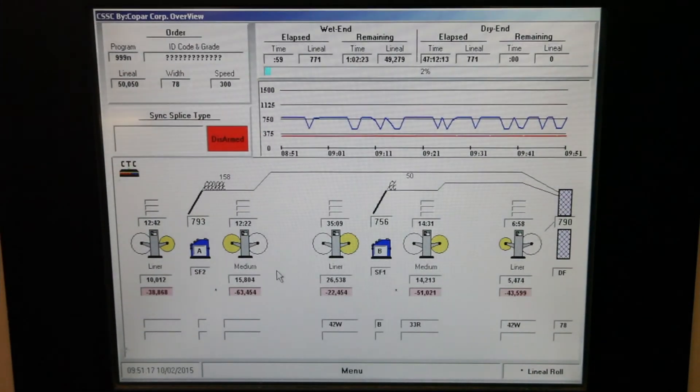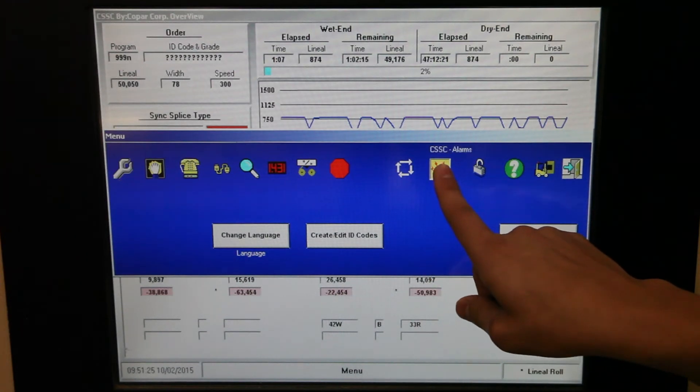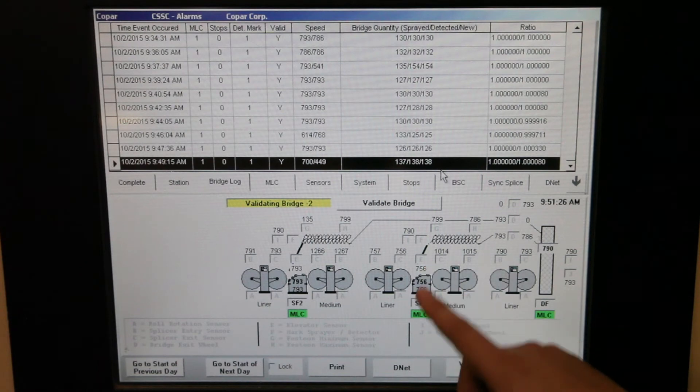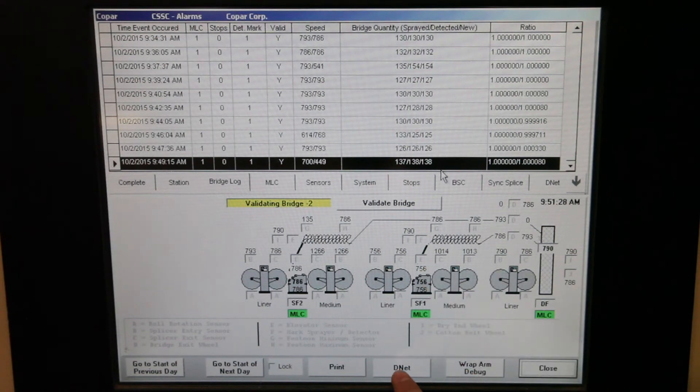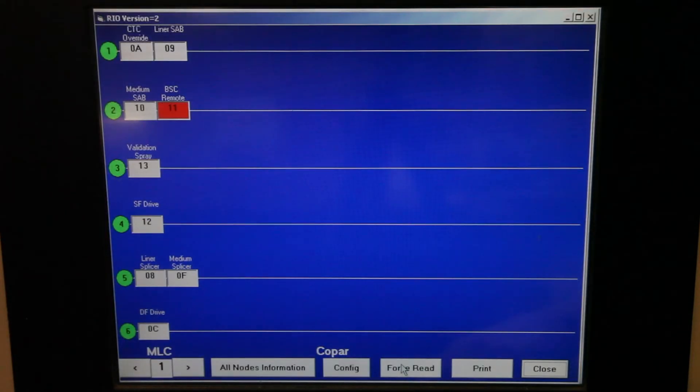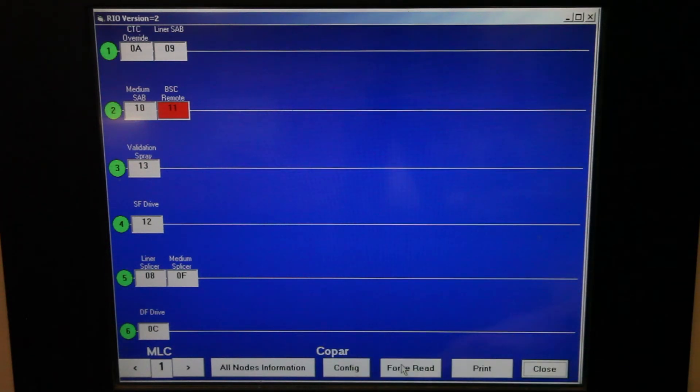This is how we get to the D-Net screen for troubleshooting. Press Menu on the bottom of the screen. Then press the icon that looks like an alarm to open the alarm screen. Press D-Net on the bottom of the alarm screen, which will bring up the D-Net status screen. What we see here is each of the six individual channels and what is actually connected on each string.